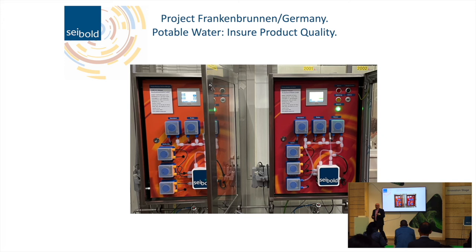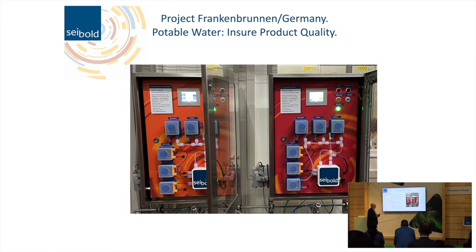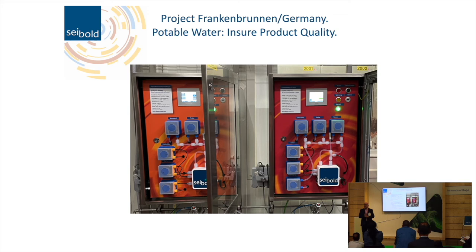Some examples from real installations. First is Frankenbrunnen, a mineral water company in Bavaria. We have an installation measuring 13 different sample streams, from raw water to quality assurance for the end product, in different time sequences. The matrix of the water is very different from sample to sample, and the measurement range we need to cover is from 0 to 10 PPM — a huge range. We cover this with two analyzers: an iron-manganese analyzer and a nitrite analyzer, with iron-manganese as a double measurement.